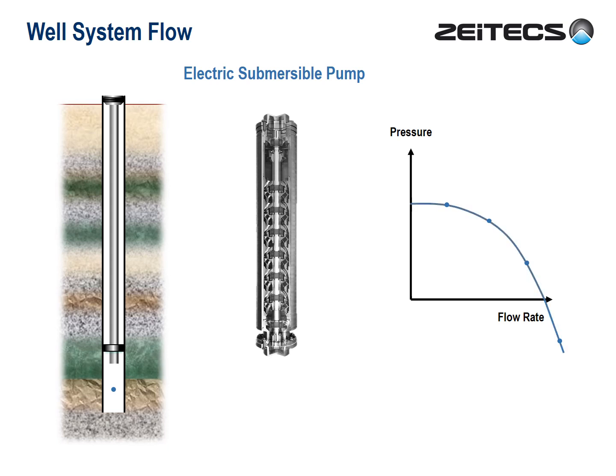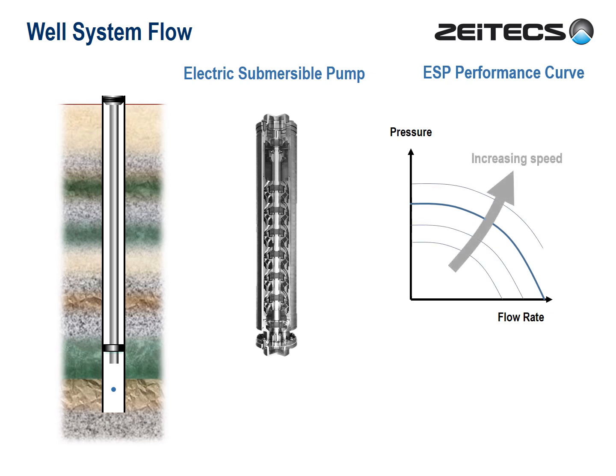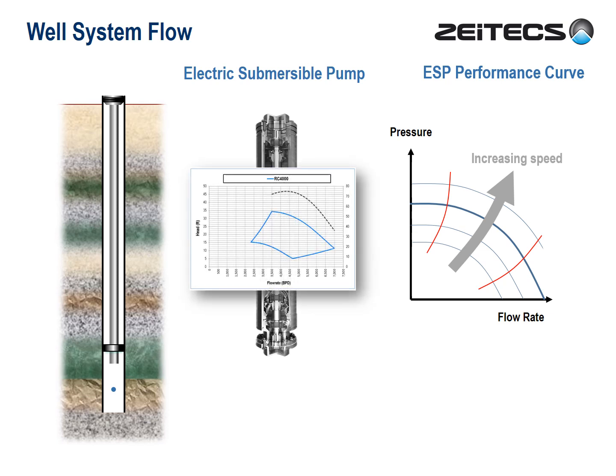So now we're building an ESP performance curve, and since this curve will vary with pump speed, we'll expand the picture for variable speeds. At the far left of these curves, the pump will struggle against the near-stationary fluid column, and the reactive forces known as down-thrust will accelerate wear. Also to the far right, the rapidly moving fluid will tend to lift the impellers, resulting in up-thrust wear. So we try to operate within these extremes. That completes our picture of an ESP operating envelope. Here is a real-life example — you'll see quite often the efficiency of a pump is also plotted.